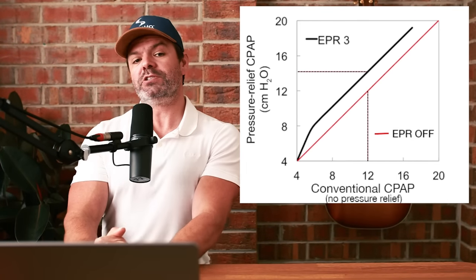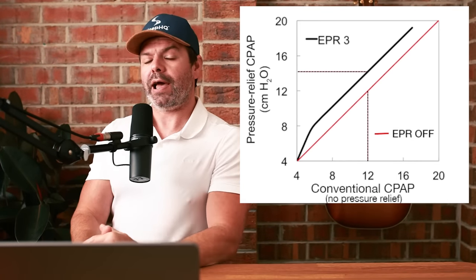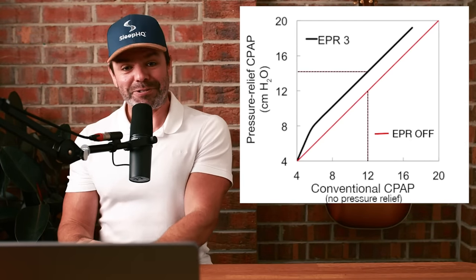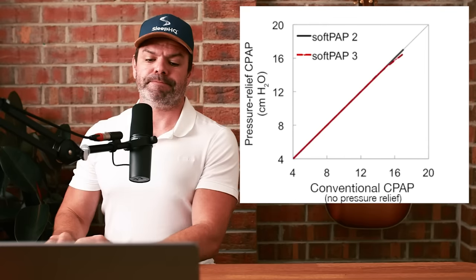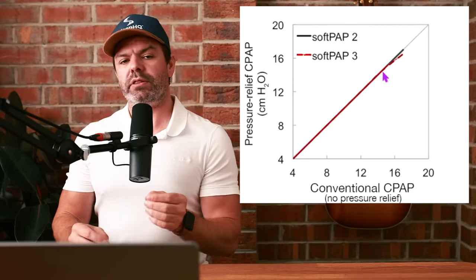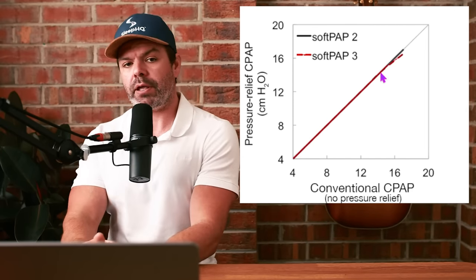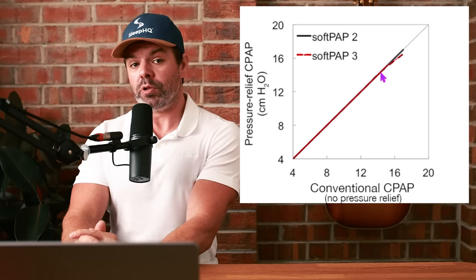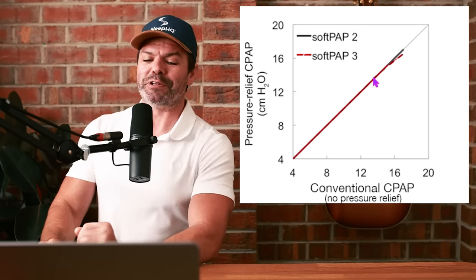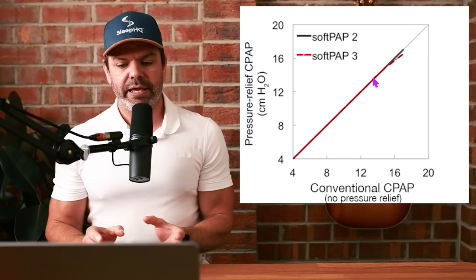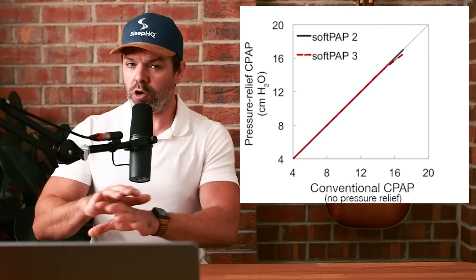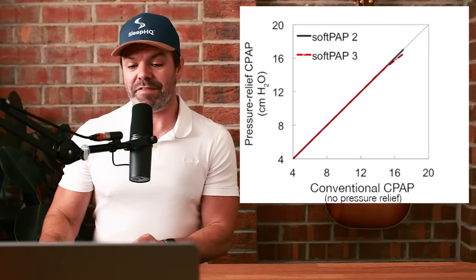What's fascinating is these researchers also took a look at some pressure relief technology from other companies, and the results are very interesting. This is the exact same pressure relief chart, but this time from a German company Löwenstein and their SoftPAP pressure relief.